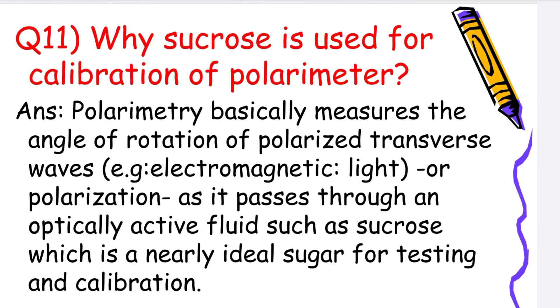Why is sucrose used for calibration of a polarimeter? A polarimeter basically measures the angle of rotation of polarized transverse waves. The light passes through an optically active fluid such as sucrose, which is a nearly ideal sugar for testing and calibration.